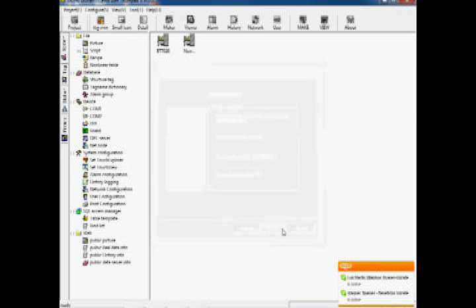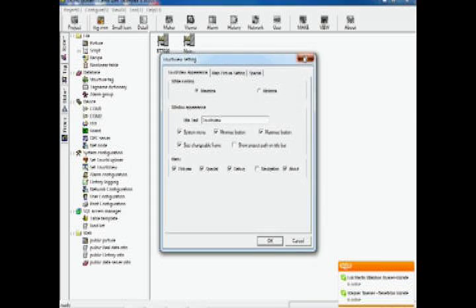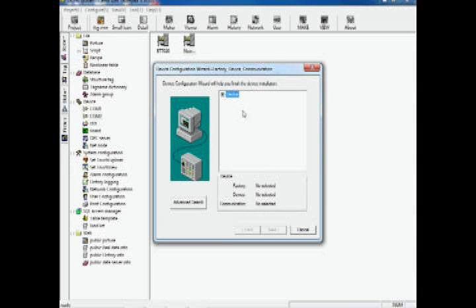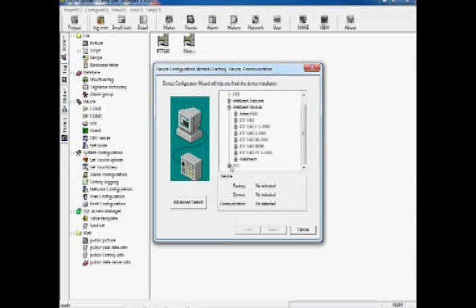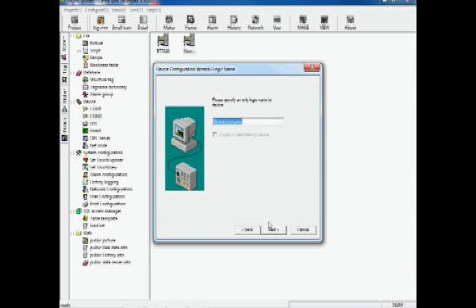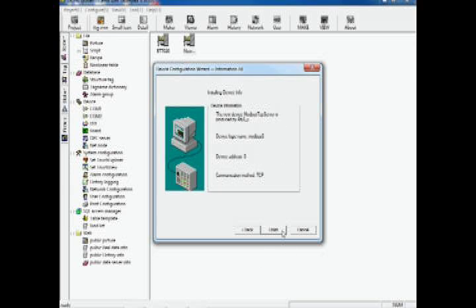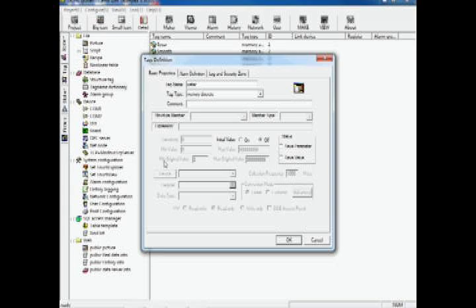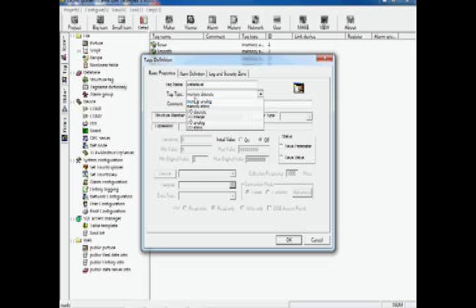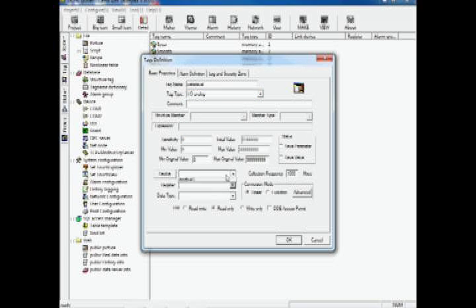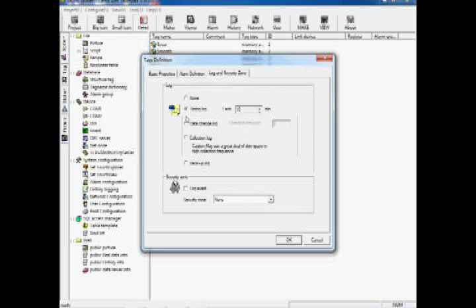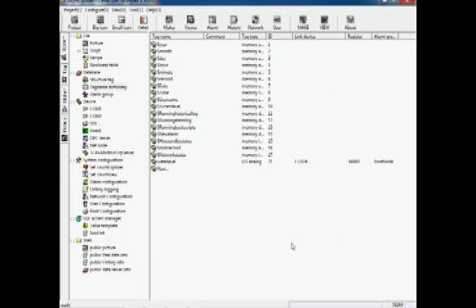At the top right of your screen, click Make on the toolbar to enter the development system. For this project, we need to connect with ET7026. We will create an I/O tag so we can get data from the module. Click Tag Name Dictionary. Double-click New. We're going to make Tag Name Water Level, Tag Type I/O Analog.